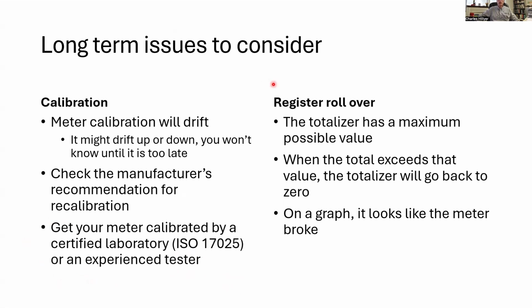One other problem that you're going to see over the very, very long term is something that I usually call register rollover. When meters have been in service for a very long time, you will see this phenomenon. It doesn't happen very often. It happens over several years, where the totalized flow will go up and up and up, and then suddenly it'll appear to drop back down to zero. Now, that totalizer is basically the result of some math, and the math is happening either in the meter's electronics or in the portal in the database on the back end. But regardless of where it happens, there is some maximum possible value that the totalizer can hold. And once the flow accumulates above that maximum value, almost all of these devices go back to zero and start over.